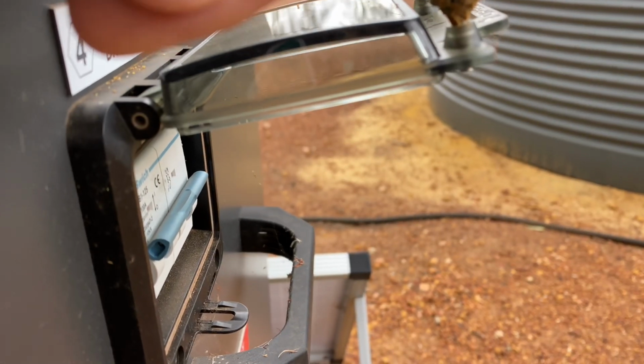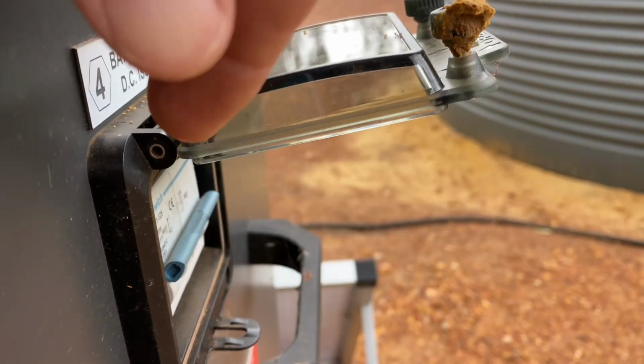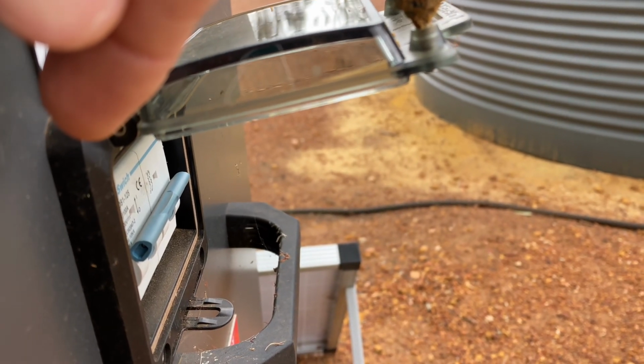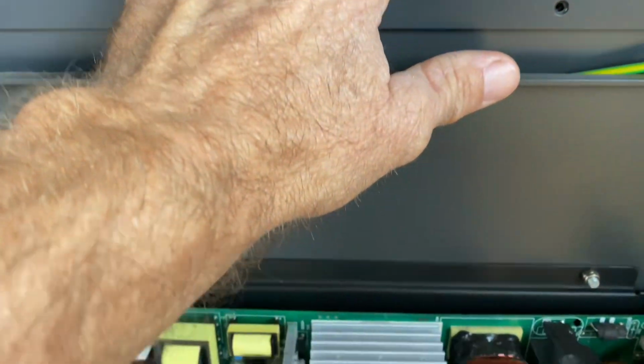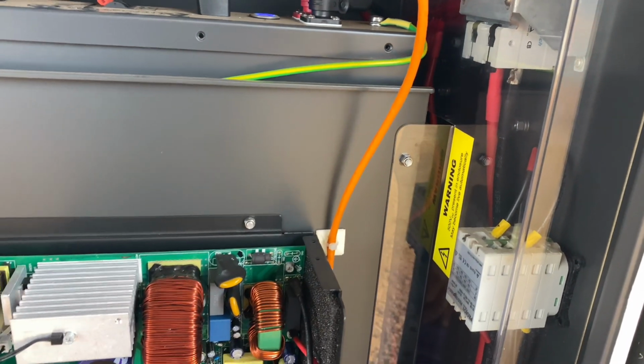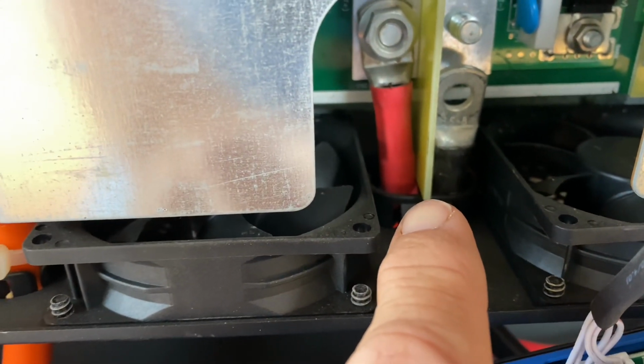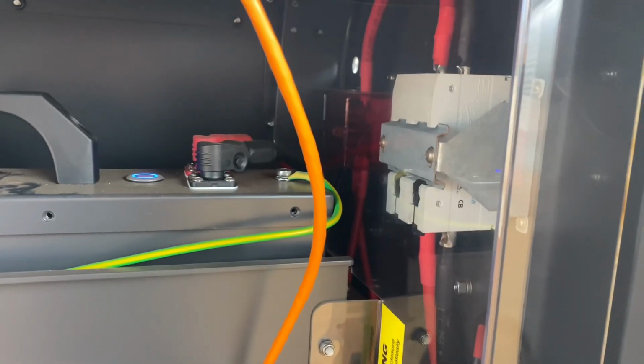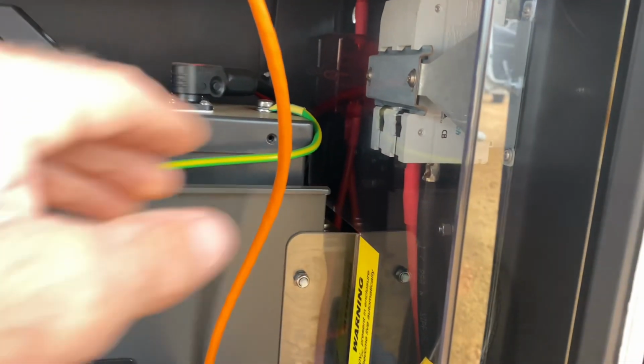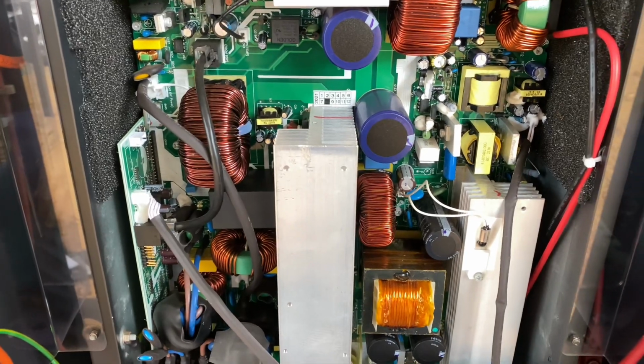At first I thought it was this DC isolator on the outside because it wouldn't reset, and he said to me it wouldn't reset, but it was actually floppy, and sometimes when they're floppy they're faulty internally. But when I actually turned the battery on and turned the circuit breaker outside there on the DC isolator, the DC isolator kept tripping. So what I've actually done is disconnected the 48 volt supply to the inverter, and everything stopped tripping. So that tells me that the battery's okay, the DC circuit breaker is okay, and we do indeed have a problem with the inverter.